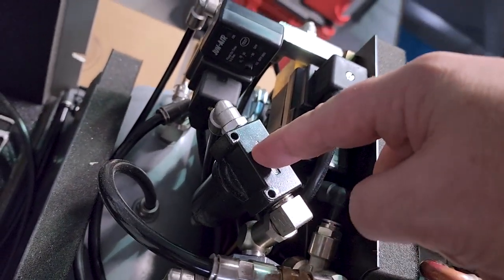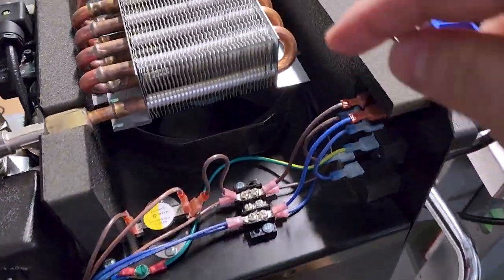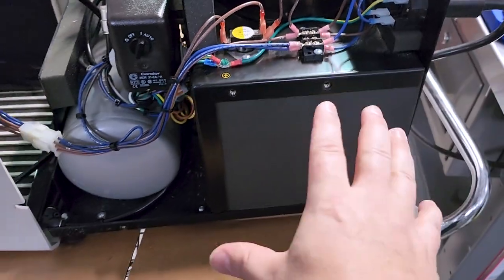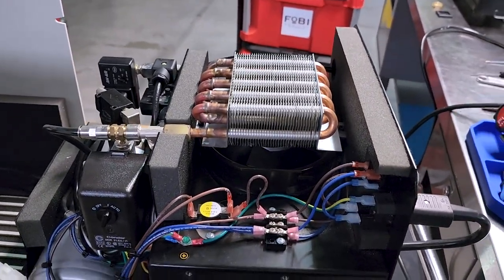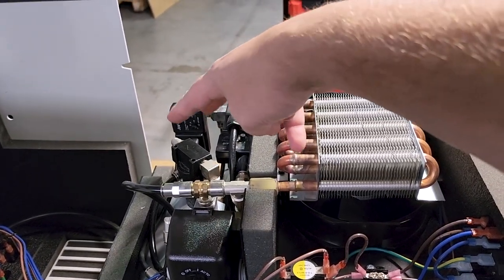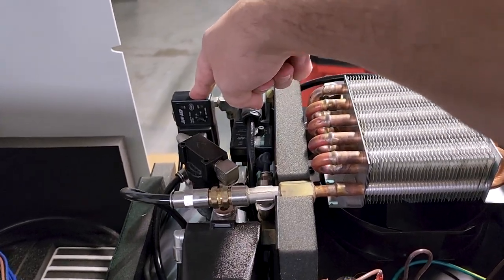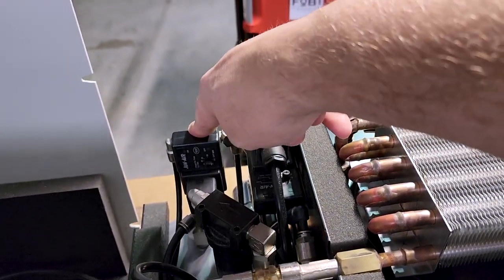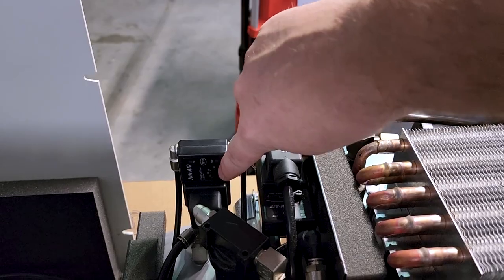So right here, we have a water separator. You can see right there, that's your pressure. And inside this reservoir right here is the actual compressor and you can barely see it right here. And mind you, these are live wires, so I got to watch it. So the compressor is housed inside this noise canceling box and that's because it's an ultra quiet. You're talking 40, maybe 50 decibels when this thing's running. It is so quiet. So your compressor is in there. It kicks on. These two valves right here, they will switch their positions. They have LED indicators and you can adjust their on time. So if you want it to purge a little bit longer, if you're in a high humidity environment, you can actually turn this guy up. You can adjust that and you adjust their duration right here.